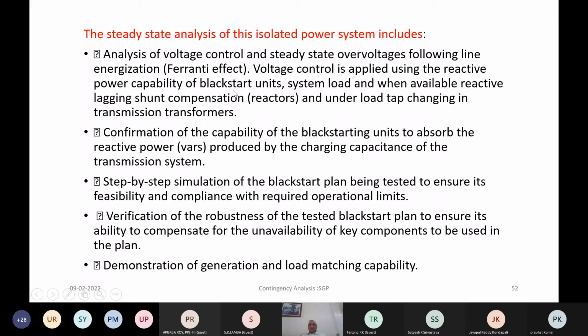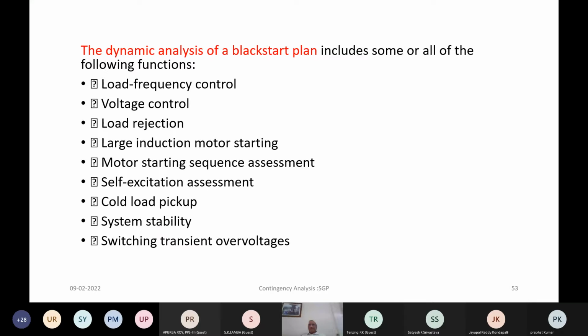This requires, for each black start facility, some study to be carried out in terms of voltage rise, etc., to take care of the Ferranti effect, as we mentioned, due to leading VARs. Reactive power absorption capacity during the line charging procedure. Step-by-step simulation of the black start plan can be done, and demonstration of the generation and load matching capability.